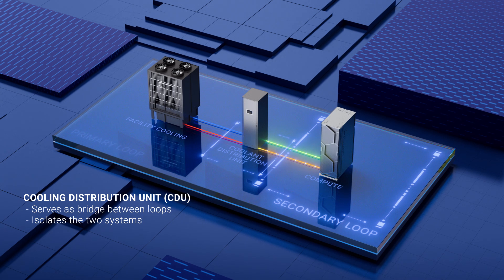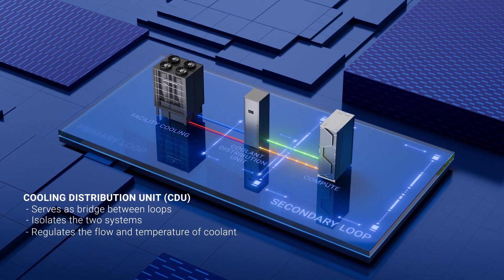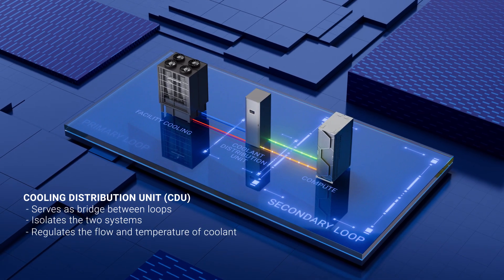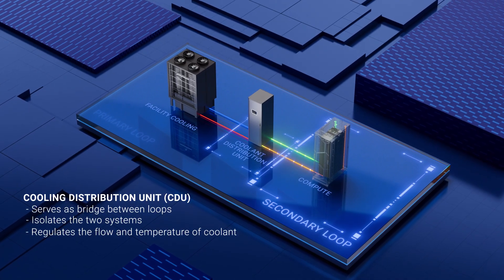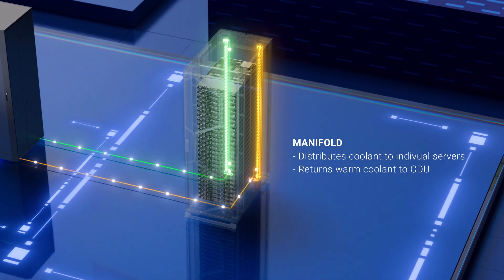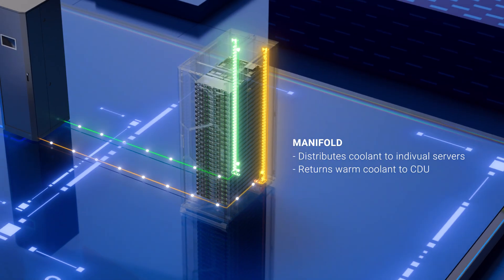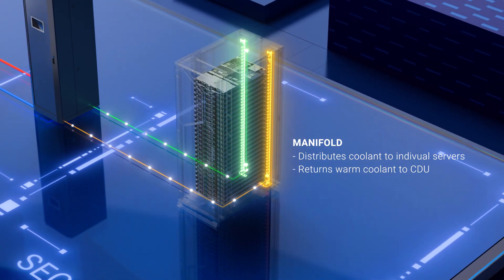Using the cool supply water from the primary network, it precisely regulates the flow and temperature of coolant throughout rack manifolds, the series of metal tubes extending the length of the rack. The manifolds distribute the coolant to individual server cold plates and return warm coolant to the CDU where the heat exchange occurs.